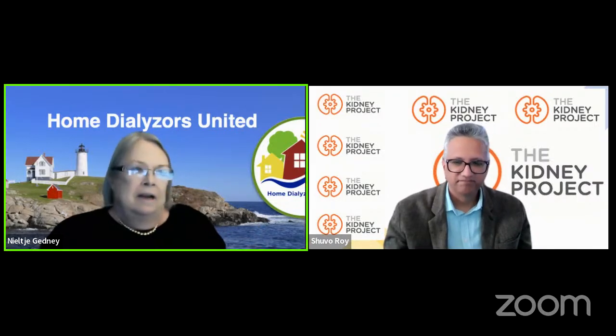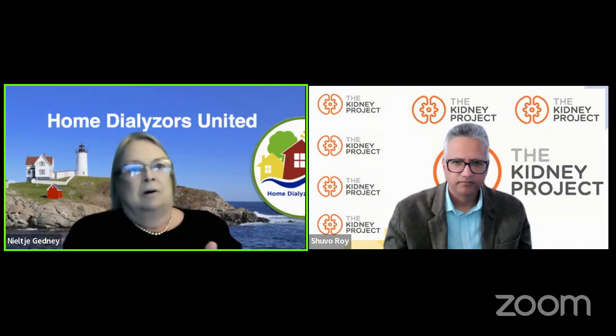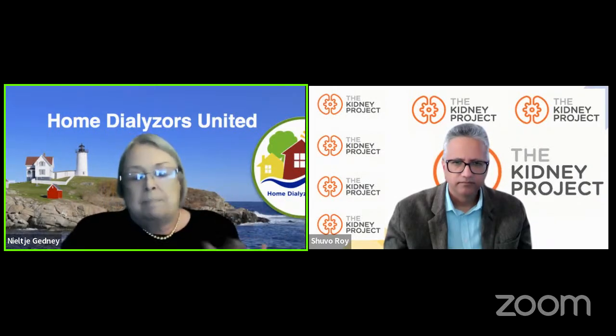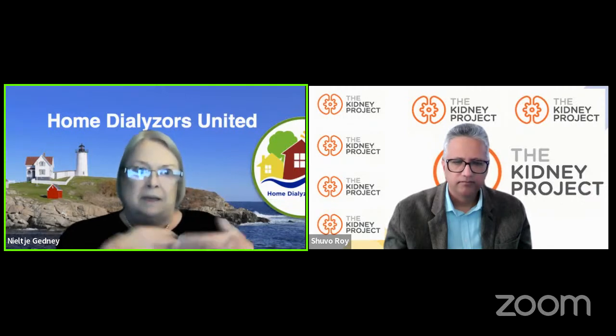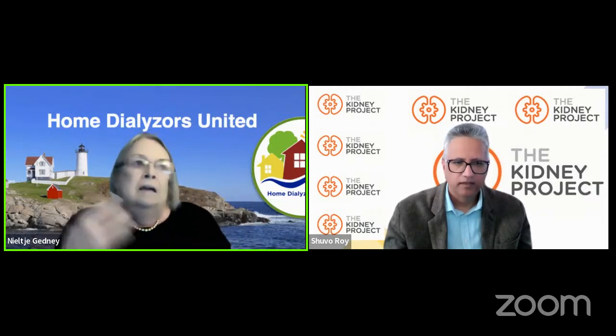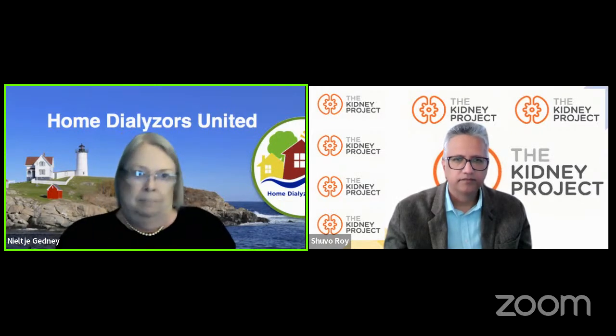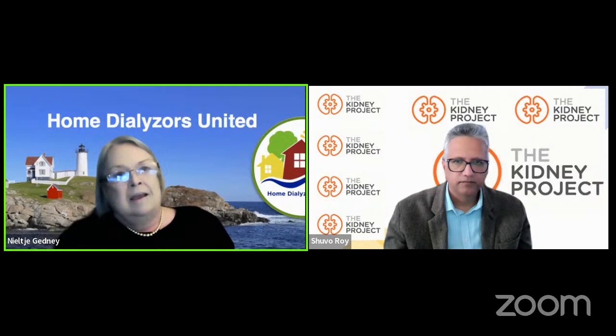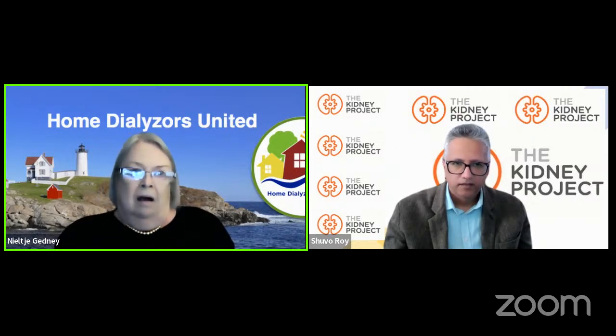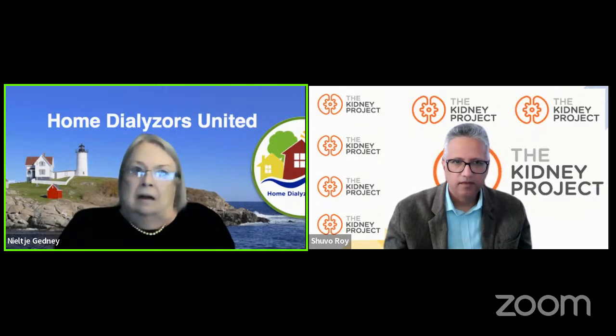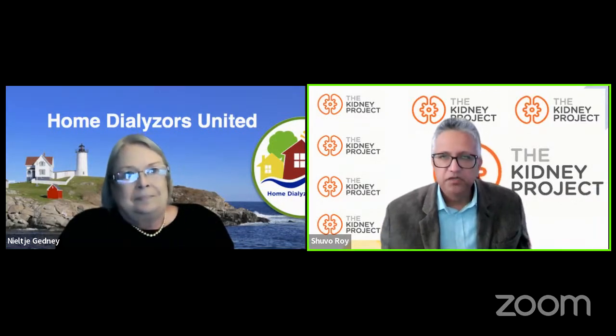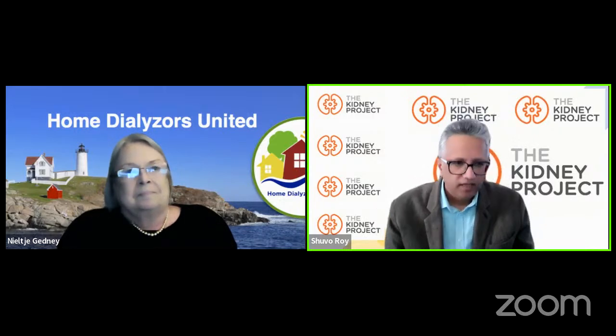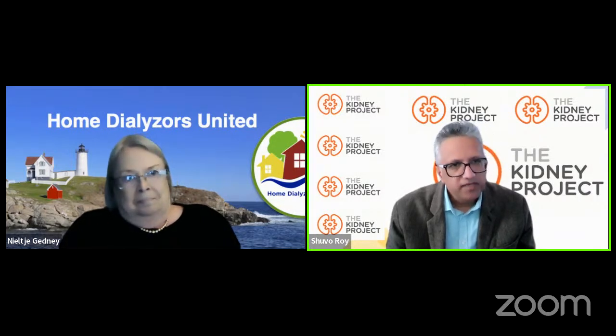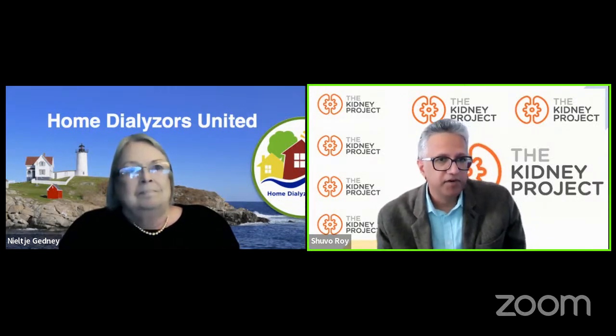So getting back to the nitty gritty: if you're using the iHemo, and you have a lot of patients doing dialysis, iHemo is going to be a dialysis type device. They may or may not have residual function, they may not be able to pee, or they might. So is the iHemo able to remove that fluid during dialysis for someone who doesn't pee? That's a great question. Can you do ultrafiltration if you don't have any residual function to remove excess fluid? Very much like regular hemodialysis, you run dialysate, but then you also apply negative pressure.